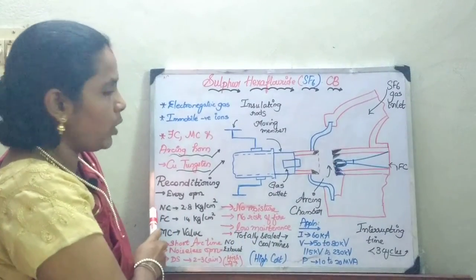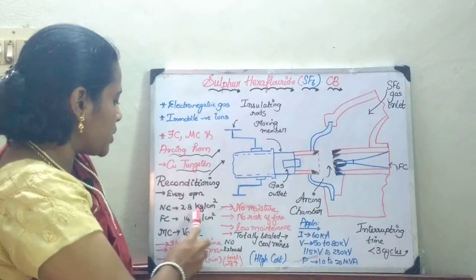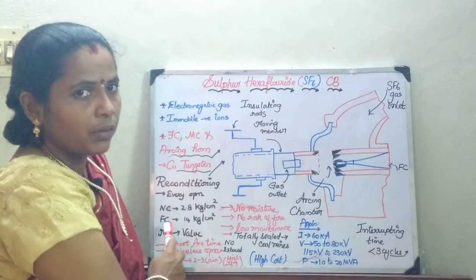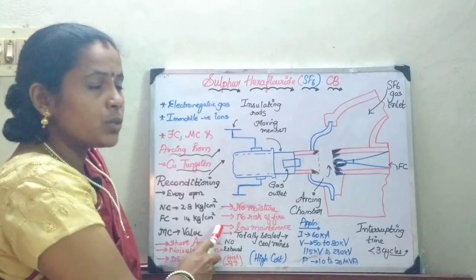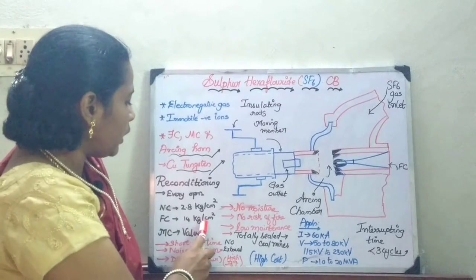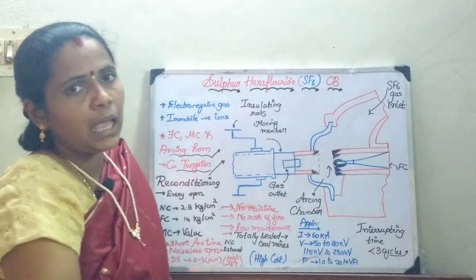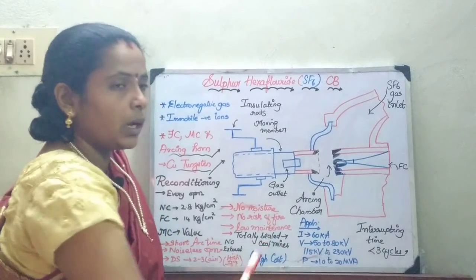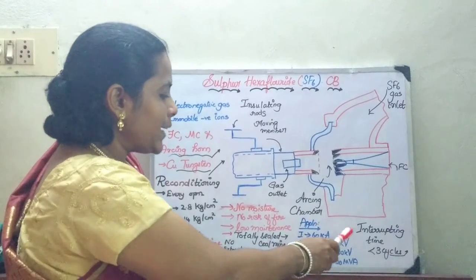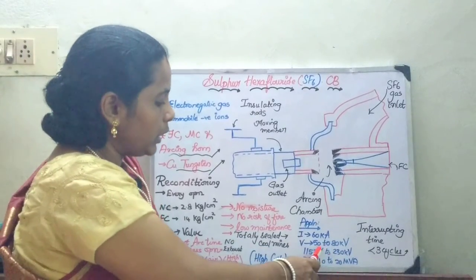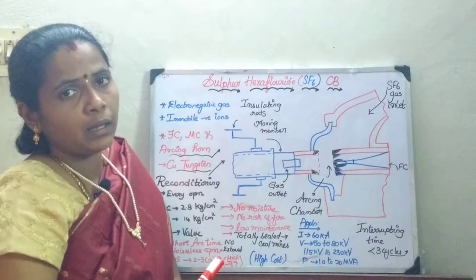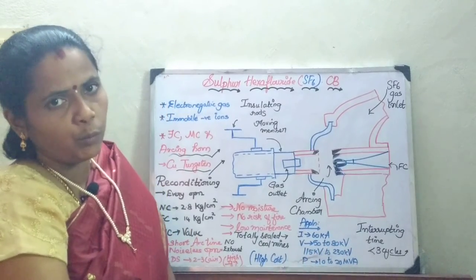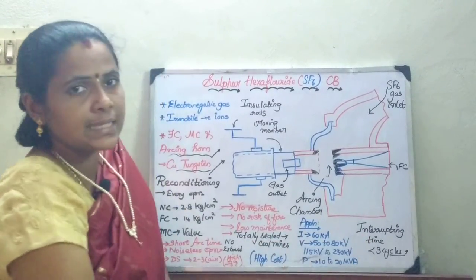Under normal conditions, the pressure is maintained at 2.8 kg/cm². But under fault conditions, the pressure is let out at a very high pressure of 14 kg/cm² in order to quench the arc as soon as possible. This proves to be an efficient circuit breaker used for interrupting a current rating of 60 kA and a voltage rating up to 80 kV, and can be used for 115 kV to 230 kV. Whereas the air blast circuit breaker was able to be used for 110 kV with a power rating of 10 to 20 MVA. The interrupting time is found to be less than 3 cycles.